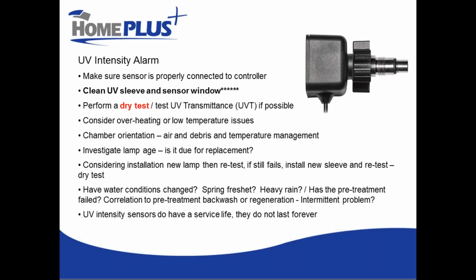Sleeves also do not last forever. If the sleeve is starting to look hazy or has deposits on it that remain after cleaning, that sleeve needs to be replaced. A lot of the manufacturers are even selling lamp and sleeve combination kits now, where they're almost giving the sleeve away because they really want you to maintain it. A fresh, clean sleeve is important, not to be forgotten.